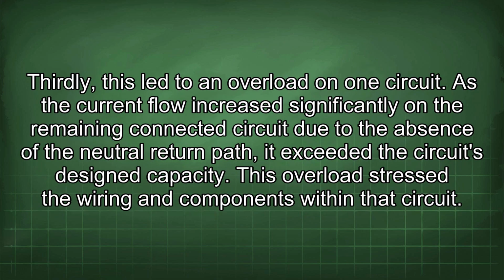Thirdly, this led to an overload on one circuit. As the current flow increased significantly on the remaining connected circuit due to the absence of the neutral return path, it exceeded the circuit's design capacity. This overload stressed the wiring and components within that circuit.